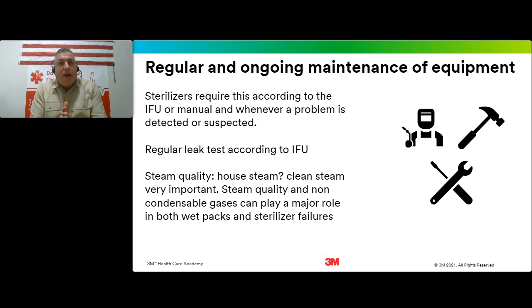But they don't, because most of us have a very robust maintenance program in place to keep our instruments nice and shiny and new and refurbished and sharp, right? Well, why don't we treat the sterilizer the same way? It's just as critical. You need to look at your chambers and really determine what you need to do. If you're cleaning annually, you should have your chambers at least looked at and potentially cleaned annually. But if you're a super busy department, you might have to step up the frequency of that. So something you want to take a look into.